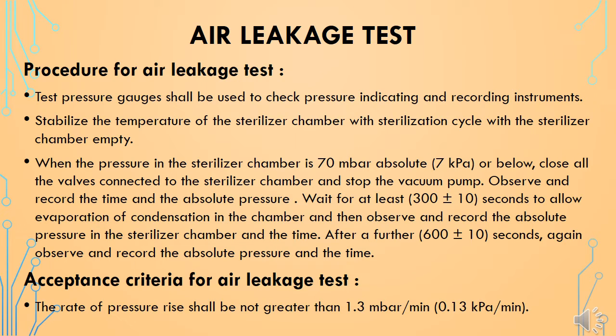For the air leakage test procedure, test pressure gauges shall be used to check pressure indicating and recording instruments. Stabilize the temperature of the sterilizer chamber with a sterilization cycle with the sterilizer chamber empty. When the pressure in the sterilizer chamber is 70 millibar absolute (7 kPa) or below, close all valves connected to the sterilizer chamber and stop the vacuum pump. Observe and record the time and absolute pressure, then wait at least 300 ± 10 seconds to allow evaporation of condensation in the chamber, and record the absolute pressure and time.